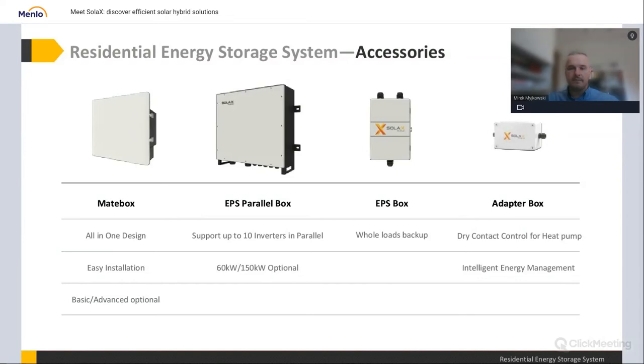The adapter box is a little box to connect our hybrid G4 inverters, and also other ones, with the heat pump. Using that, you can turn the heat pump, which has to be SG ready, into a high level of work to use extra PV energy that would normally go to the grid, using that PV energy to boil water and accumulate the energy as hot water. So your hybrid system doesn't have only one energy storage in batteries - it also has another energy storage as hot water in a boiler.